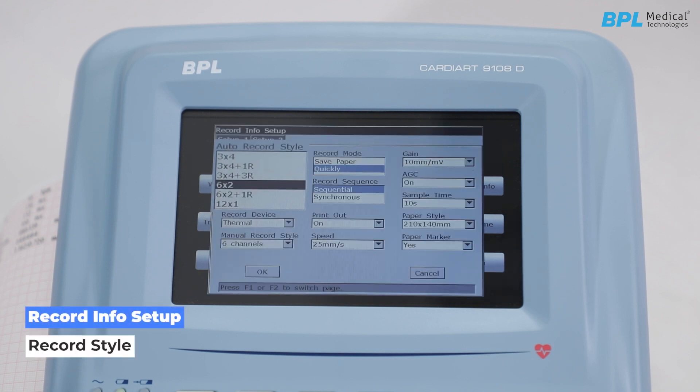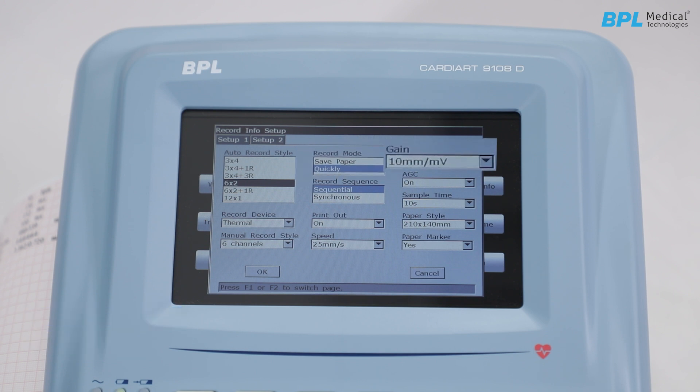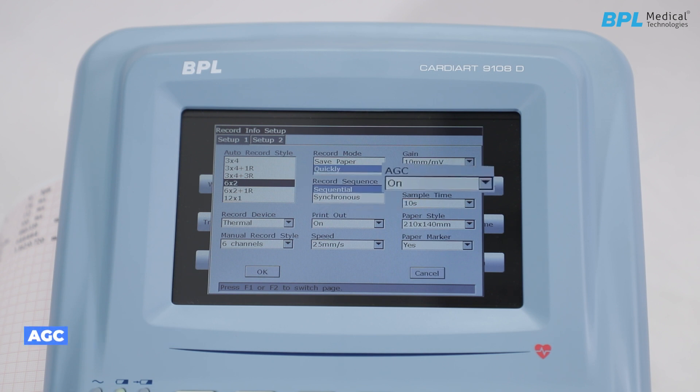In record info setup, record style sets the print format for the printout. Record mode includes Save Paper, which prints after a 10-second sampling on a single paper, and Quick mode, which prints immediately in a detailed layout. Gain is 10 mm/mV by default. Record sequence allows leads to be printed sequentially or synchronously. AGC (auto gain control) automatically adjusts gain according to actual signals. Record device is set to thermal printer by default; an external printer can also be selected. If printout is off, the ECG report will be saved without printing.